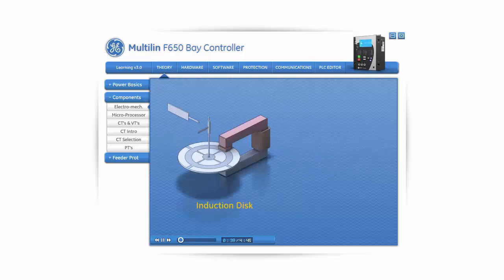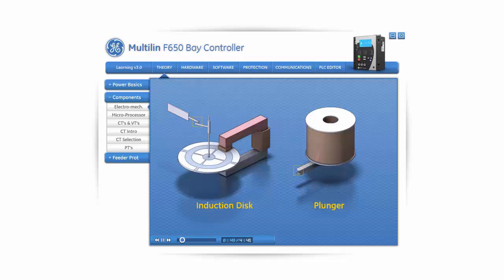In electromechanical relays, a moving part like a disc or a plunger is placed in a magnetic field produced by the input signals, known as actuating signals or measured quantity. The disc or the plunger moves and touches a contact when the intensity of the magnetic field exceeds a preset limit. Electromechanical relays fall into one of four styles or categories depending on the type of moving part. These are the plunger, the hinged armature, the induction disc, and the induction cup.